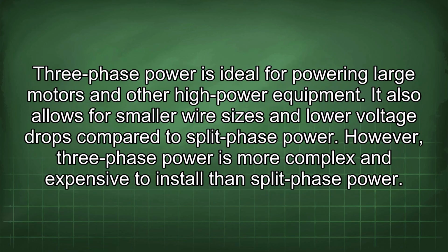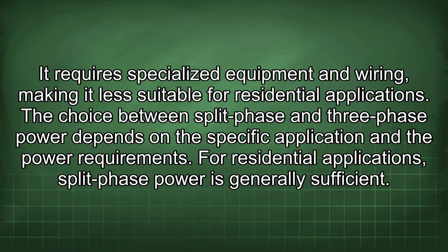Three-phase power is ideal for powering large motors and other high-power equipment. It also allows for smaller wire sizes and lower voltage drops compared to split-phase power. However, three-phase power is more complex and expensive to install than split-phase power. It requires specialized equipment and wiring, making it less suitable for residential applications.